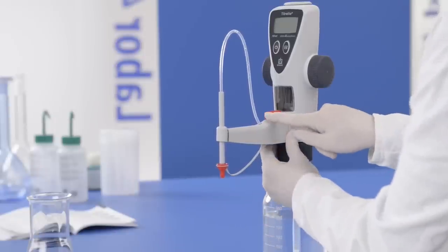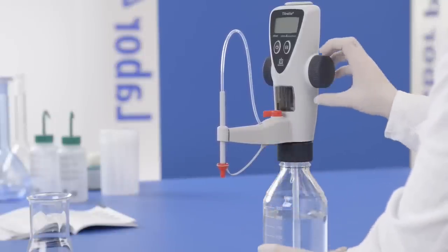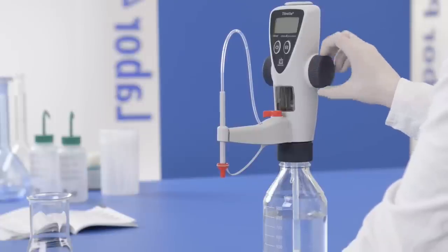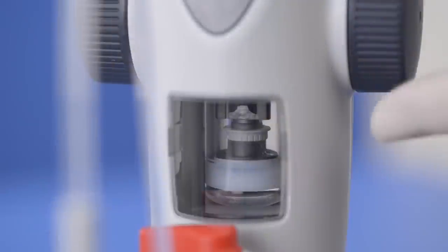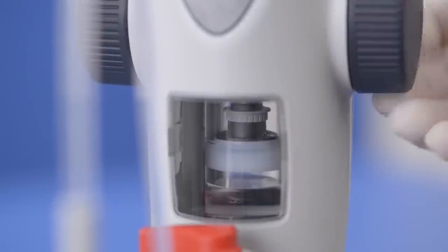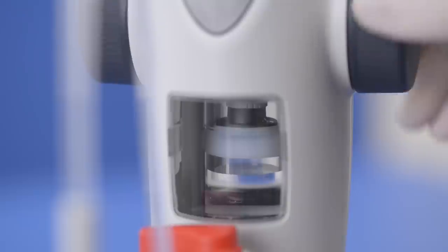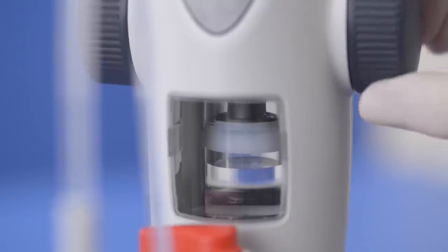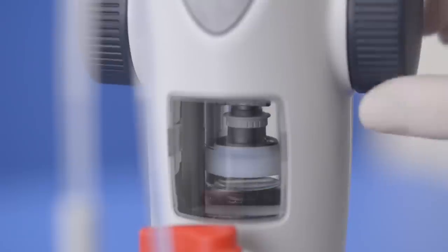Now set the valve to recirculate and check during filling whether there are air bubbles in the dispensing cylinder. If so, priming will be necessary. To do this, turn the piston halfway up then empty it again.